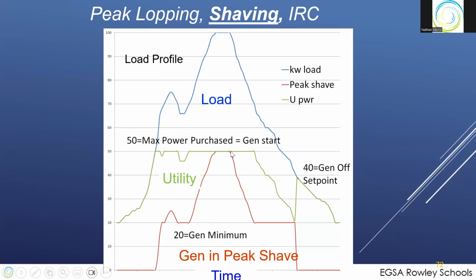As we started to come off in the afternoon, again, the load came down to some point where we could safely shut off. We're not stopping right at 50. We have hysteresis in here to keep from stopping and starting, so we actually come at some other point. In this case, in my example, I said 40. We shut the generator off and let the utility take on the load.